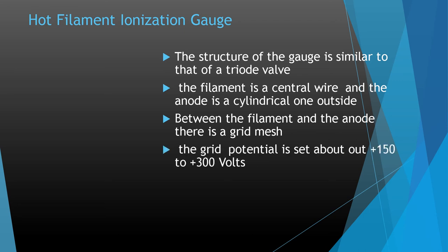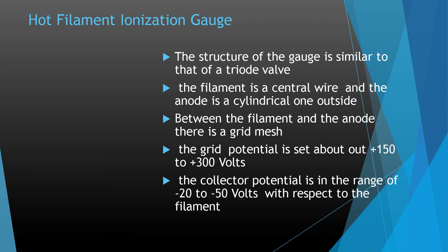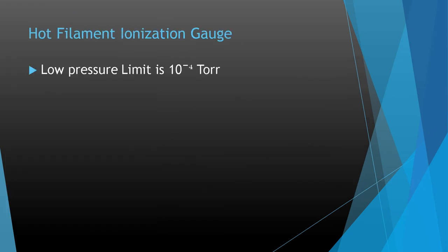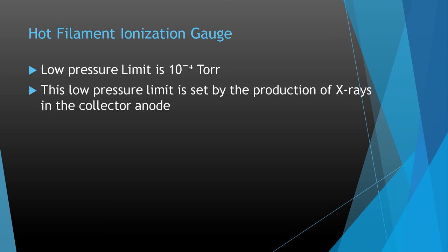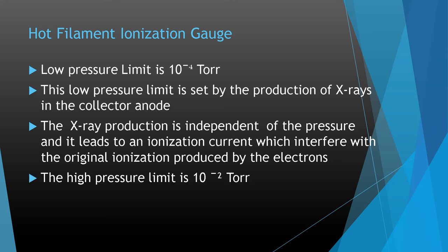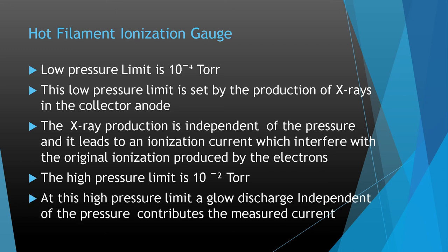The grid potential is set at about +150 to +300 volts. The collector potential is in the range of −20 to −50 volts with respect to the filament. The lower pressure limit is 10⁻⁷ Torr, which is set by the production of X-rays at the collector anode. The X-ray production is independent of pressure and leads to an ionization current that interferes with the original ionization produced by the electrons. The high pressure limit is 10⁻² Torr, at which a glow discharge independent of pressure contributes to the measured current.